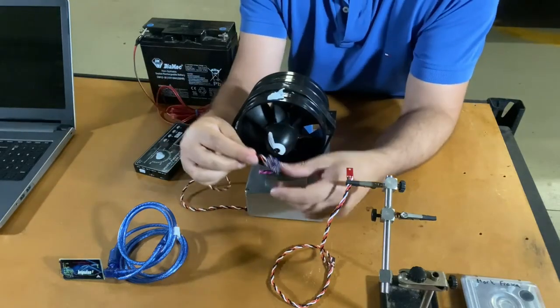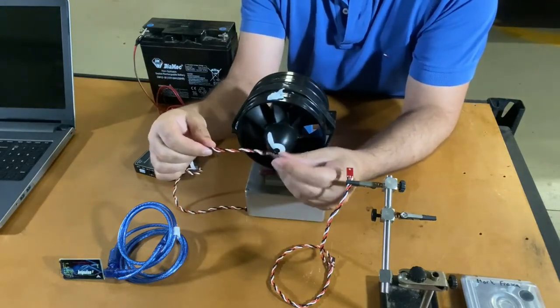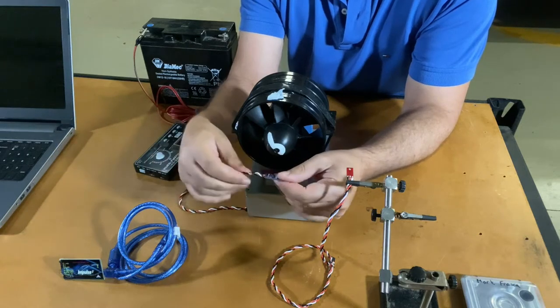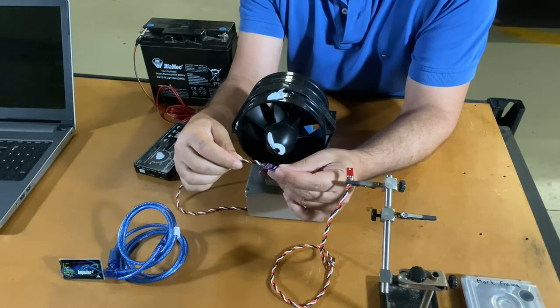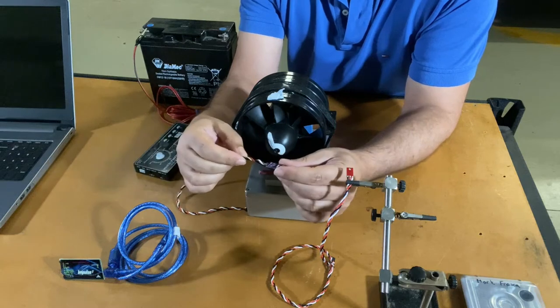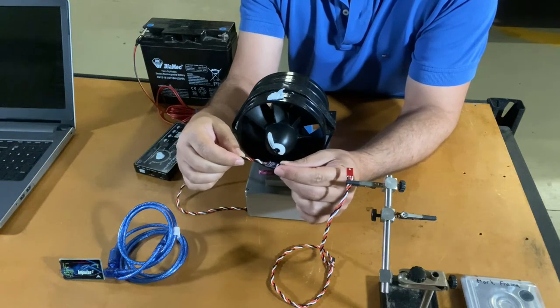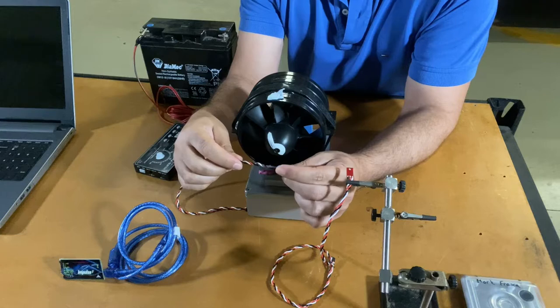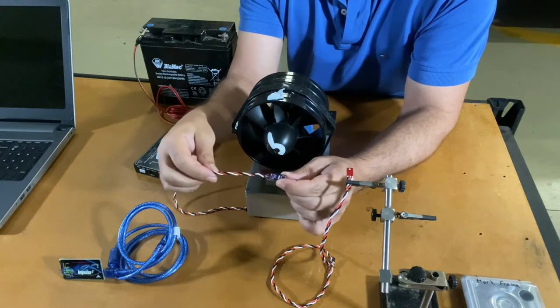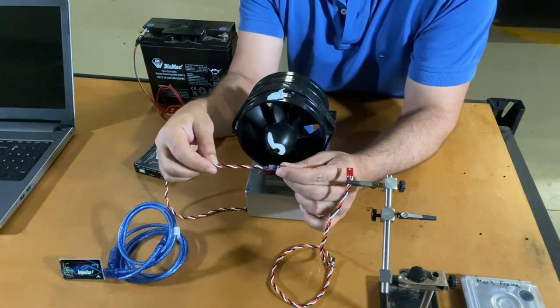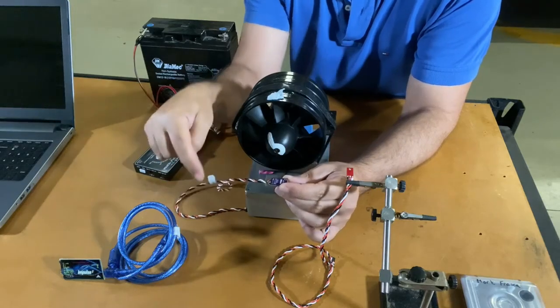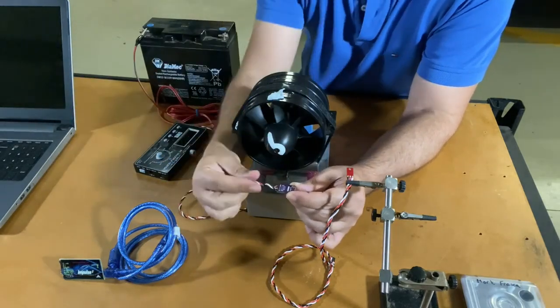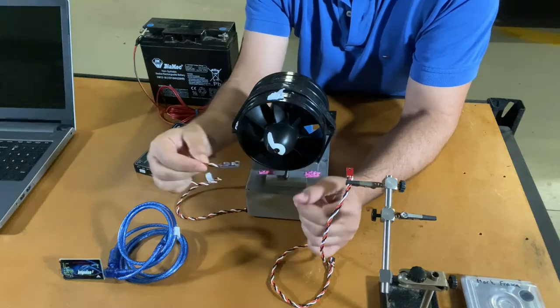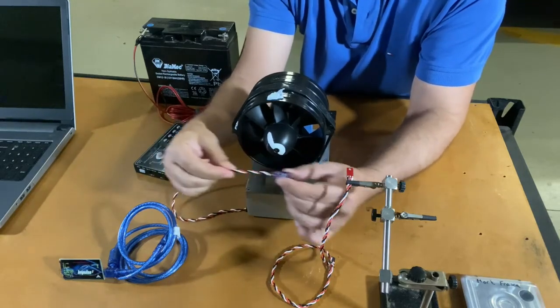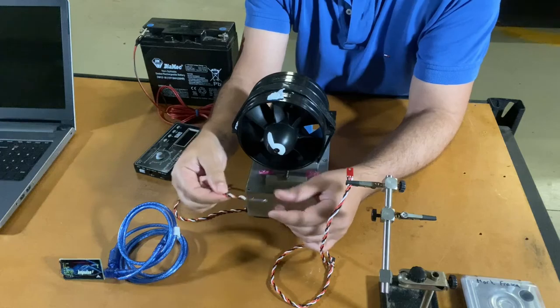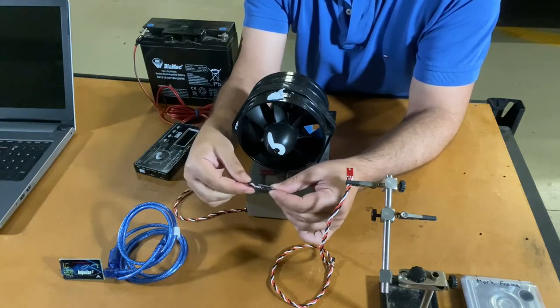So when you receive this in the kit, that's the accelerometer. The accelerometer is just a sensor for measuring acceleration, of course, in one direction in this case. The direction of the sensor is in line with the tail of the lead. So the tail of the lead is running in this direction, so the sensor will be measuring the vibration along the tail direction. So we can go ahead and mount that on top of the EDF.